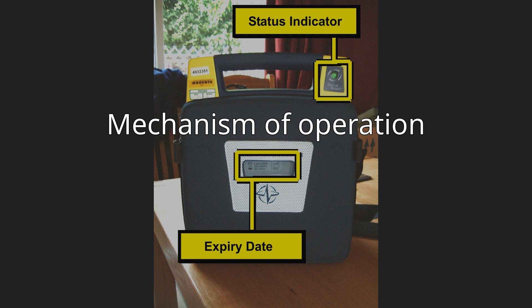Human intervention is usually required to deliver the shock to the patient in order to avoid the possibility of accidental injury to another person, which can result from a responder or bystander touching the patient at the time of the shock. After the shock is delivered, most devices will analyze the patient and either instruct CPR to be performed or prepare to administer another shock. Many AED units have an event memory which stores the ECG of the patient along with details of the time the unit was activated and the number and strength of any shocks delivered. Some units also have voice recording abilities to monitor the actions taken by personnel in order to ascertain if these had any impact on the survival outcome. All this recorded data can be either downloaded to a computer or printed out so that the providing organization or responsible body is able to see the effectiveness of both CPR and defibrillation.